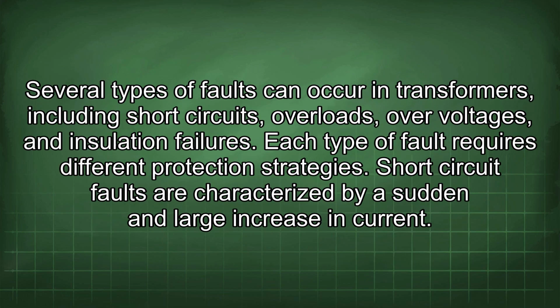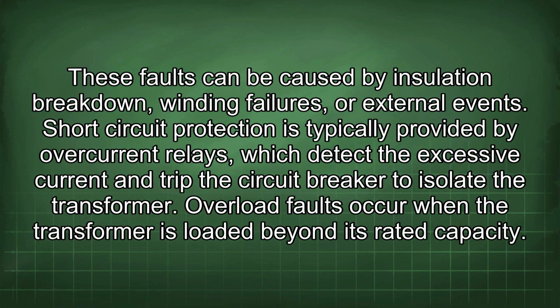Several types of faults can occur in transformers, including short circuits, overloads, overvoltages, and insulation failures. Each type of fault requires different protection strategies. Short-circuit faults are characterized by a sudden and large increase in current. These faults can be caused by insulation breakdown, winding failures, or external events. Short-circuit protection is typically provided by overcurrent relays, which detect the excessive current and trip the circuit breaker to isolate the transformer. Overload faults occur when the transformer is loaded beyond its rated capacity.